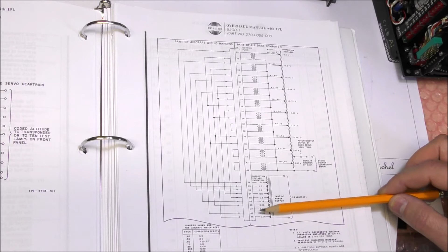There is a specific transformer in order to set a specific AC voltage at each tap of this potentiometer, and the primaries of this transformer are available on the rear connector here. There is also this transformer which generates several accurate voltages, and the user can connect each primary here to a specific voltage in order to set a specific correction for a given Mach number.